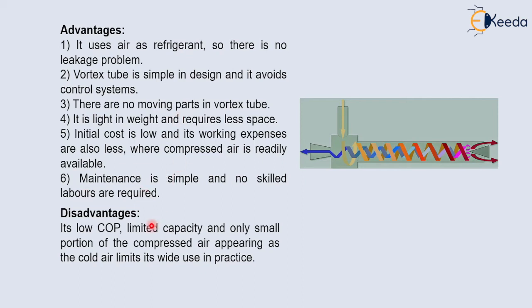The disadvantages of the vortex tube refrigeration system are: it has low COP; it has limited capacity, meaning it can only be used for small capacity plants; only a small portion of the compressed air appears as cold air, which limits its wide use in practice; and the cold compressed air coming from the cold side has limited applications.